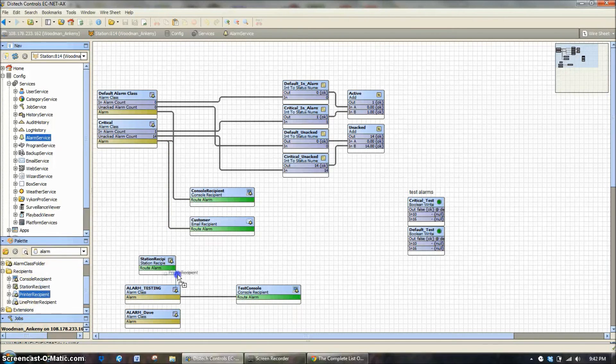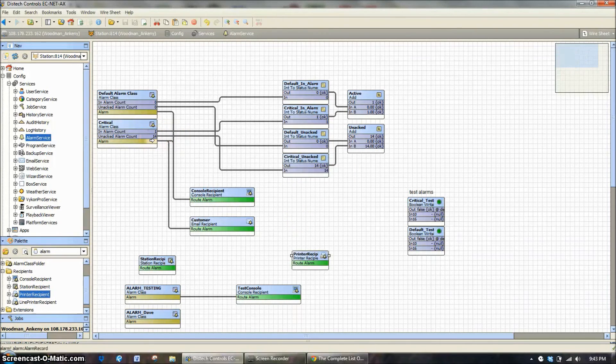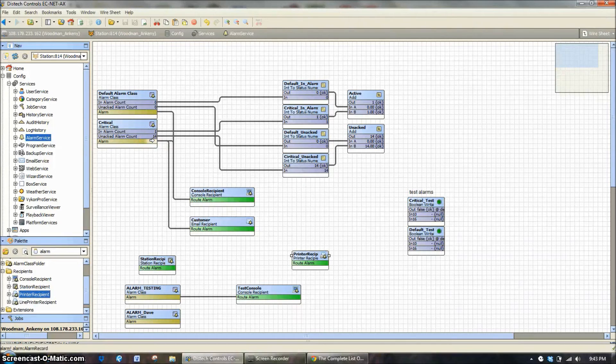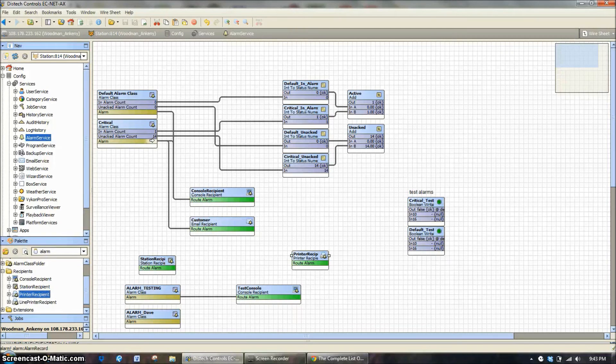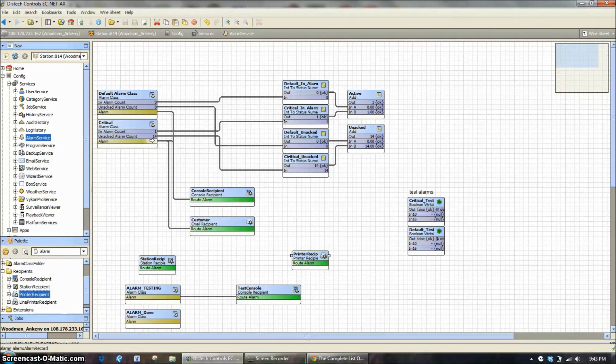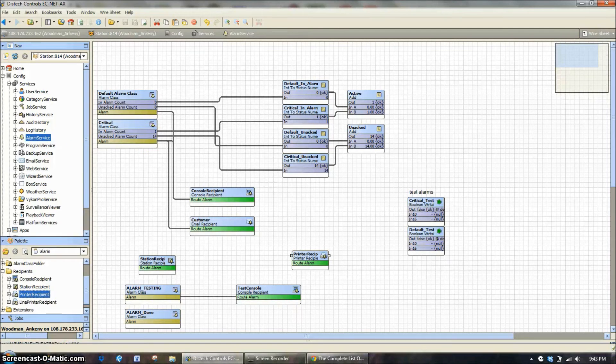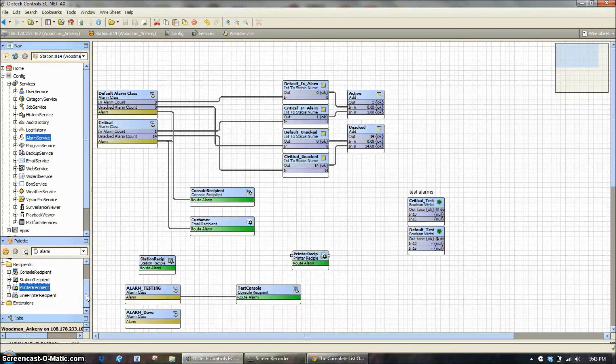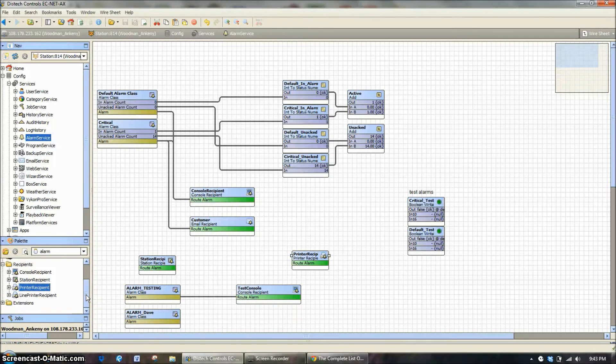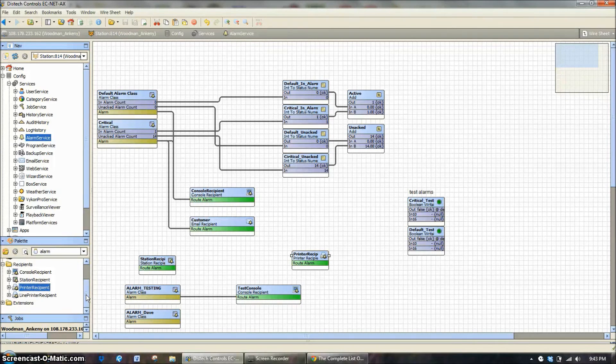Printer recipient, just like you would think. You could select this to go to just critical, or perhaps you want this to be just maintenance alarms. So in the maintenance shop, you have a printer that is just printing out a continuous copy of maintenance requests. The maintenance requests could be dirty filters or a fan failure alarm or runtime alarms so that you know when you have to grease bearings or change belts. And then finally, line printer recipient. We frankly don't have a whole lot of line printers out there anymore. But if you have a line printer that you want to print out one item at a time, one alarm at a time, is kind of a running rolled list. That's how you would do it there.